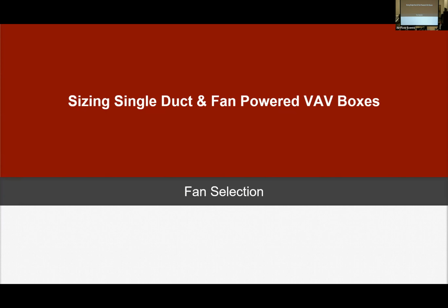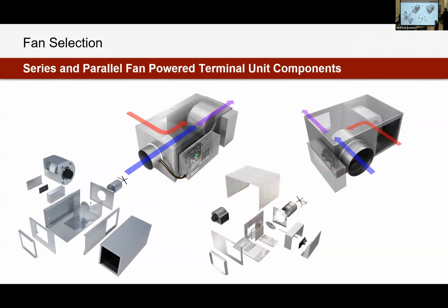All right, we will get away from single ducts and start talking about fan powered boxes now and fan selection. Now this is not your duct mounted fans. Again, this is still a fan inside of a terminal unit. So we have an inlet valve, but we also have a fan. Your two types of fan powered boxes are series and parallel. At the end of the day, they both do the same thing. It's an inlet valve and a fan, but you're controlling them differently.